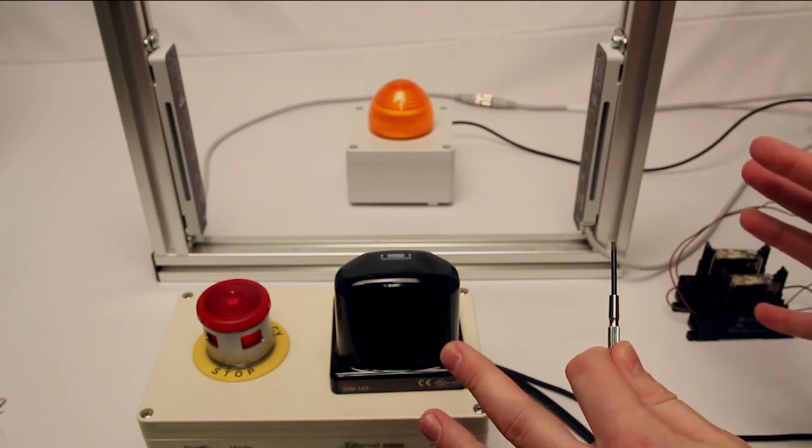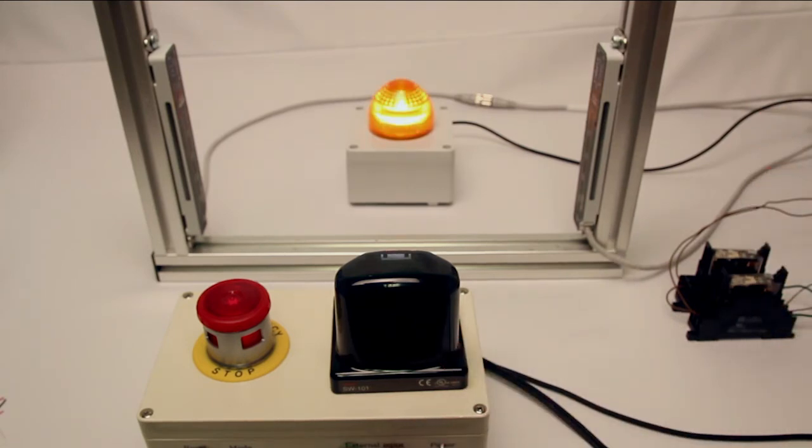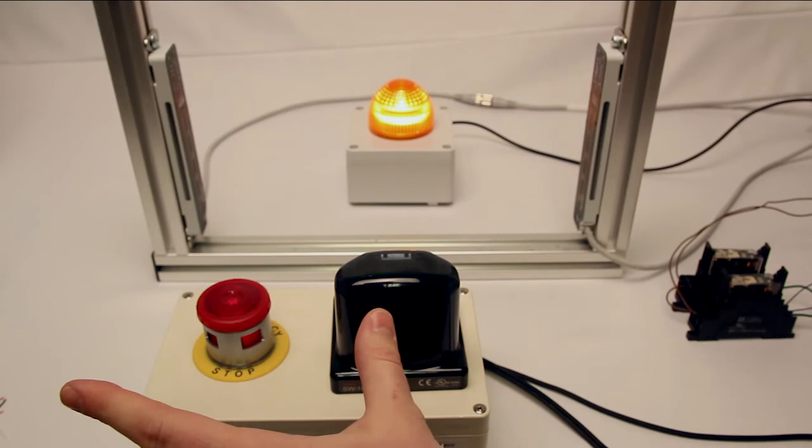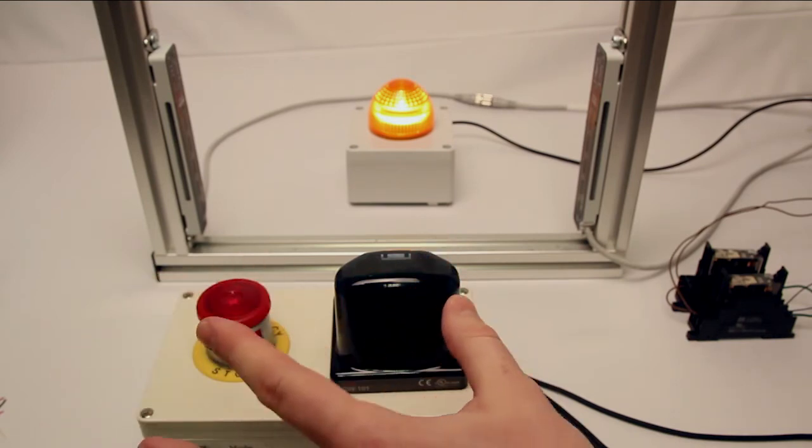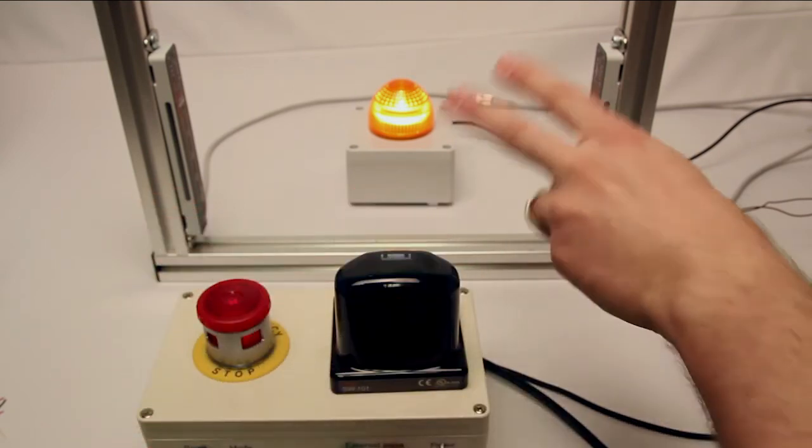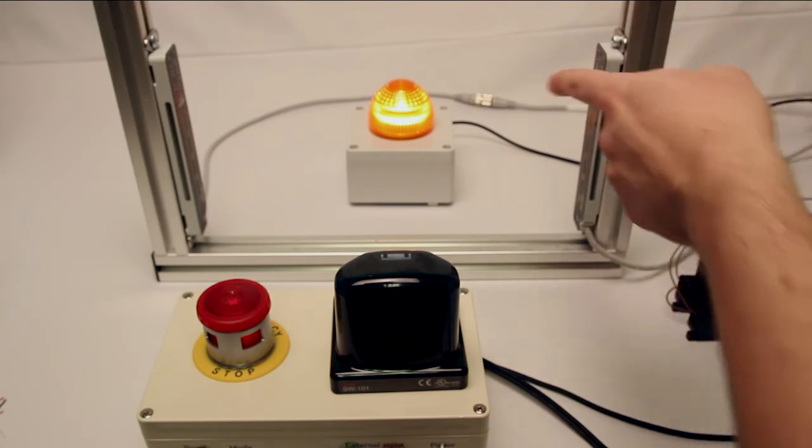It's all fed into the same safety circuit. There is no extra controller needed. So I can have a whole array of extra peripherals that all need to do the same thing, and they all go straight into those two safety inputs to shut the machine off.